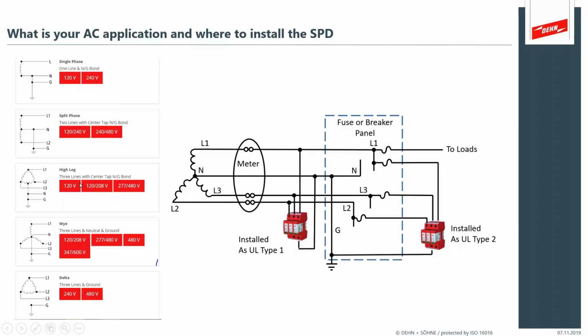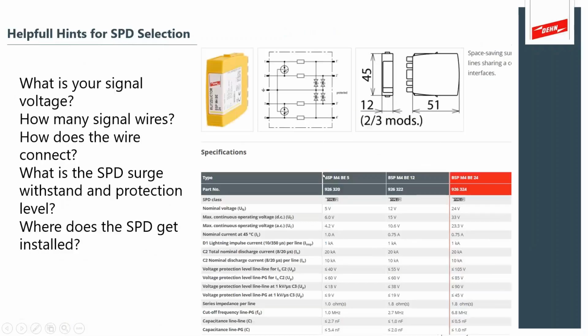We have very helpful tools on our website where it's easy to pick out your electrical service, and it gets you to a product in just a few clicks. So it's easy to pick out the right products if you know your system voltage, which comes right off of your system transformers and panels. And it's important to understand, are you installing upstream of the breaker directly across the line without fuses because you can meet the short circuit current rating, or do you need to be installed off of fuse disconnect means, installed downstream from the fuse or your breaker panel?